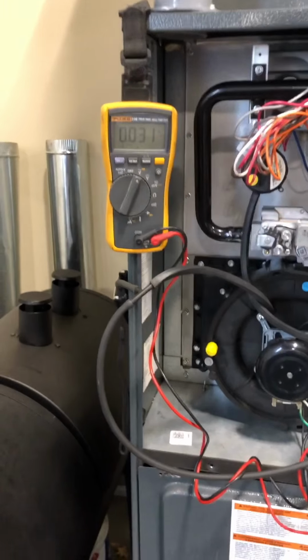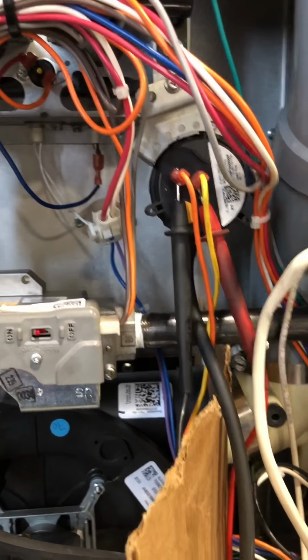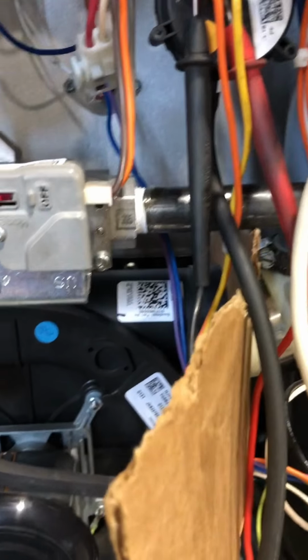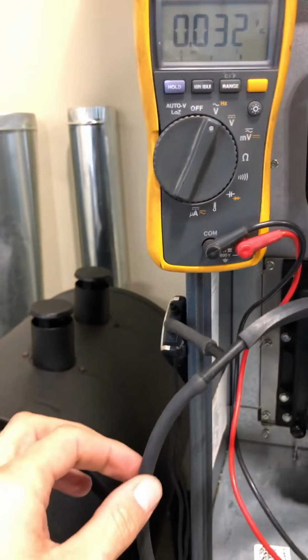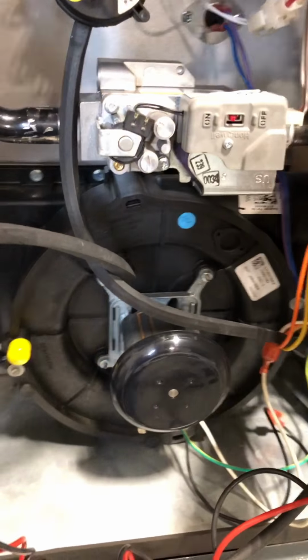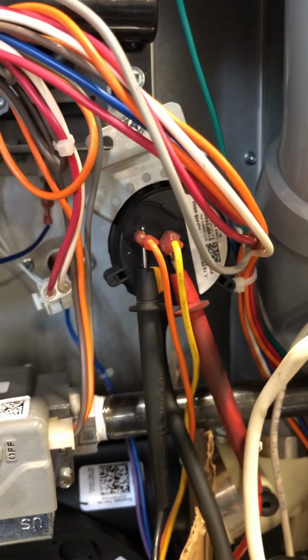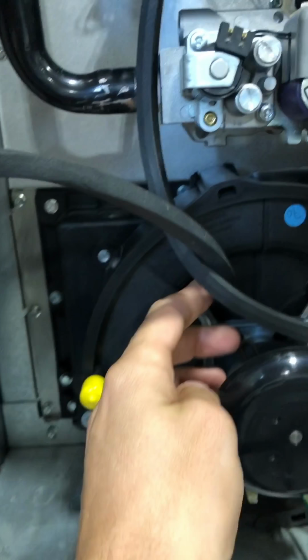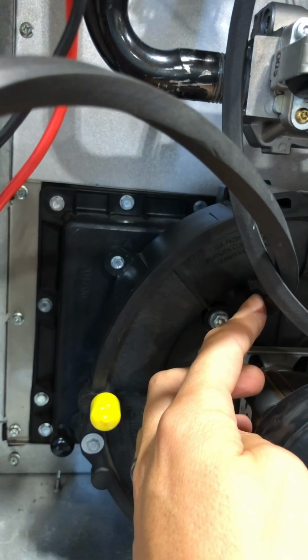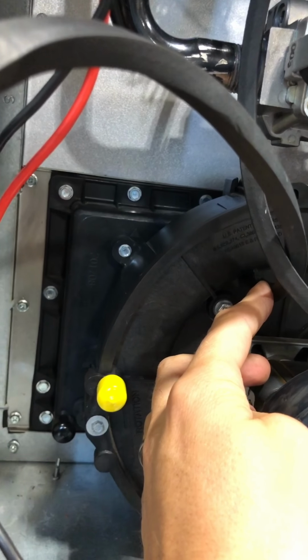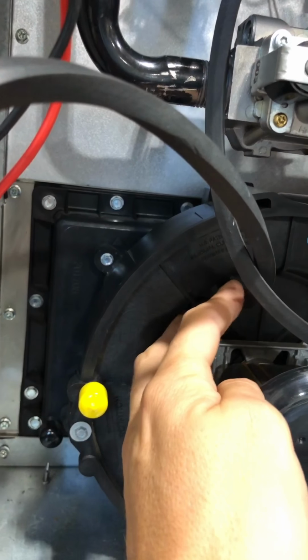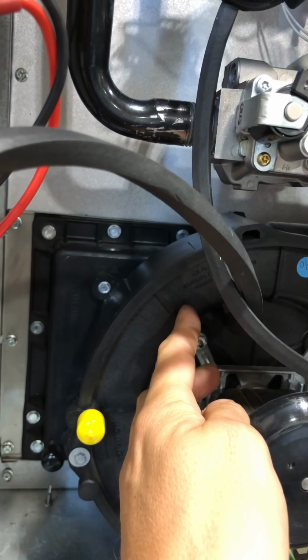All right, so what I got set up here is I got my multimeter hooked across that pressure switch in there. I also have my manometer hanging on the side over here, hooked in series with that pressure switch. It's hooked to right here on the inducer motor, so that's where we're reading our negative pressure draw off of, to make sure that this is actually pulling a negative pressure inside that heat exchanger.